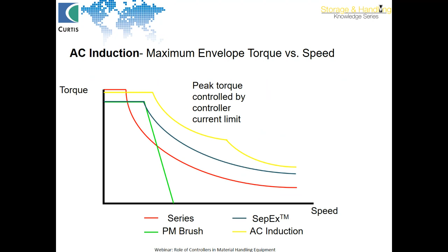There are two regions of operation of an AC induction motor. The base speed is the point marked here, midway somewhere, from where the torque starts reducing. We start defluxing the motor, so the torque starts falling because at this point the applied RMS voltage has risen to the maximum rating available from the battery. Suppose your battery is 100 volts, then by square root you get up to 64 volts max voltage.